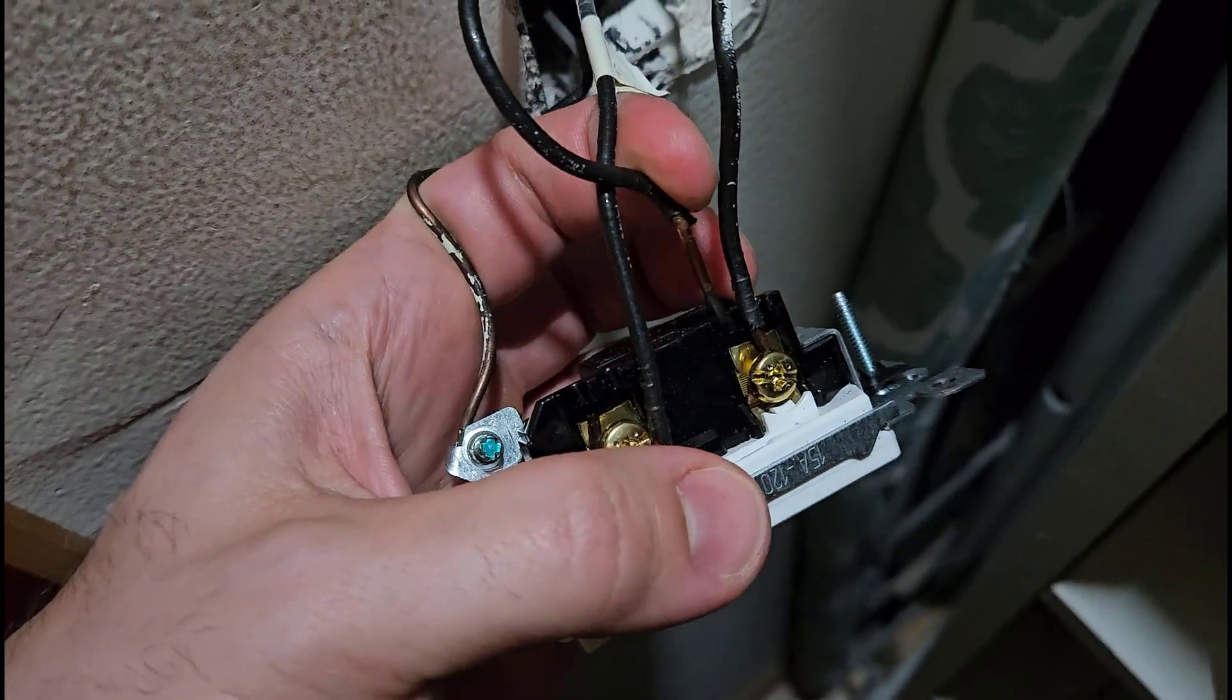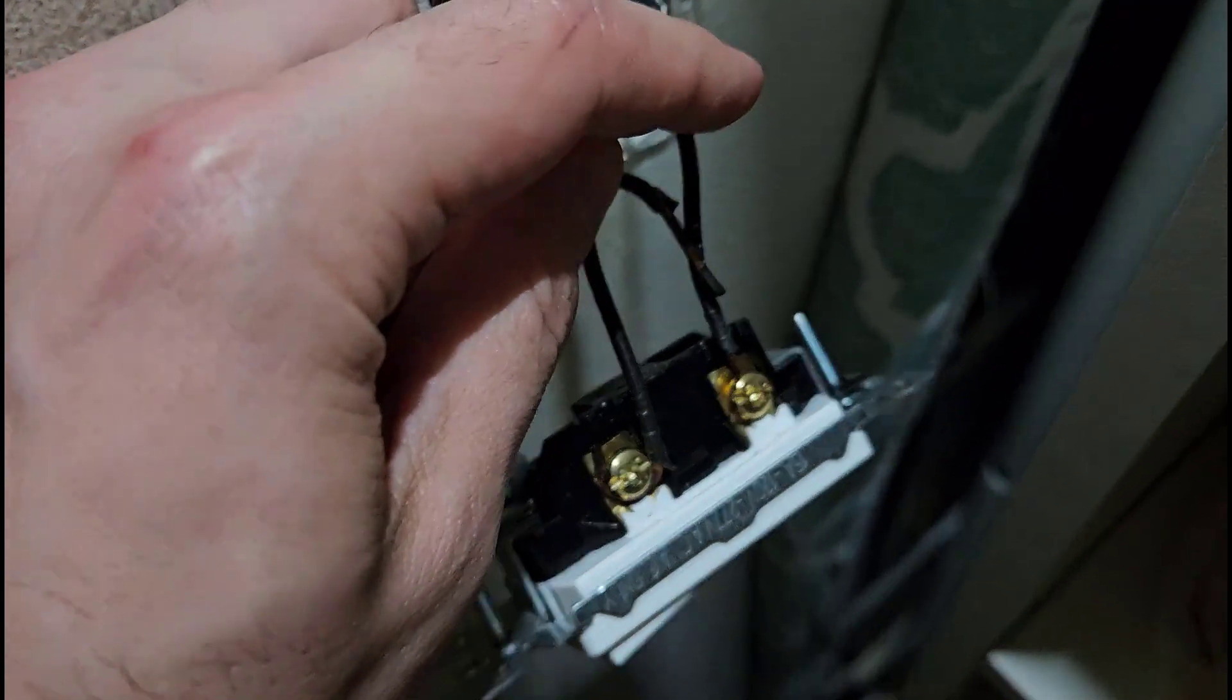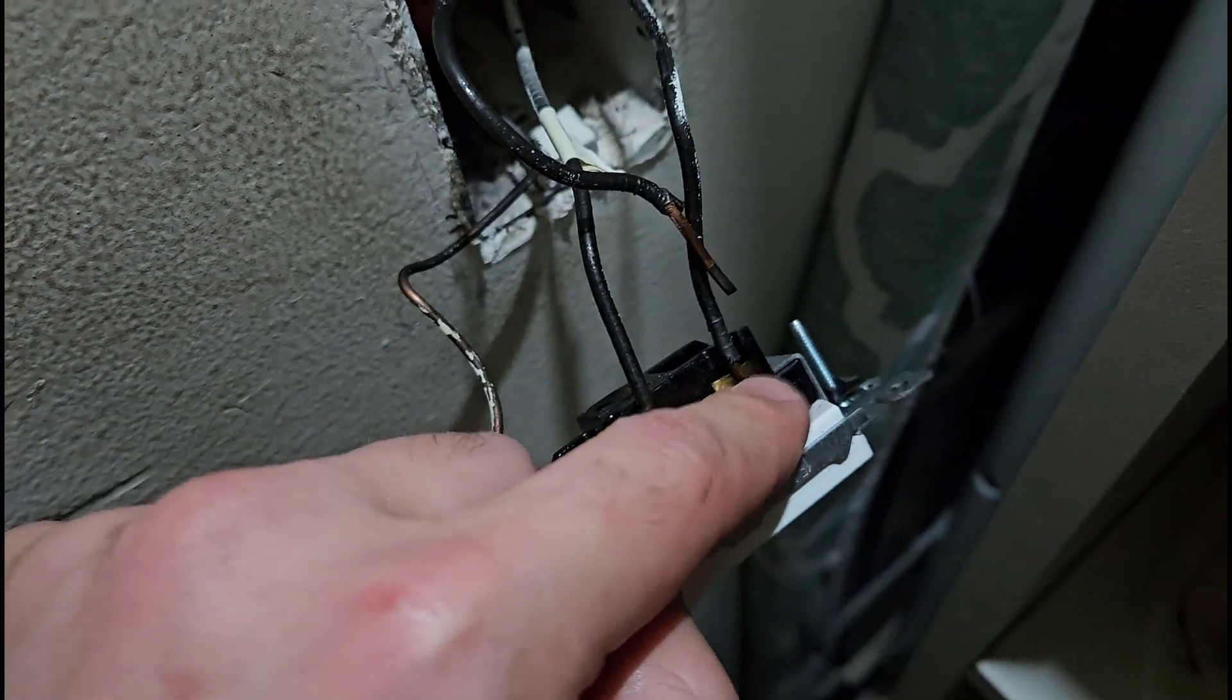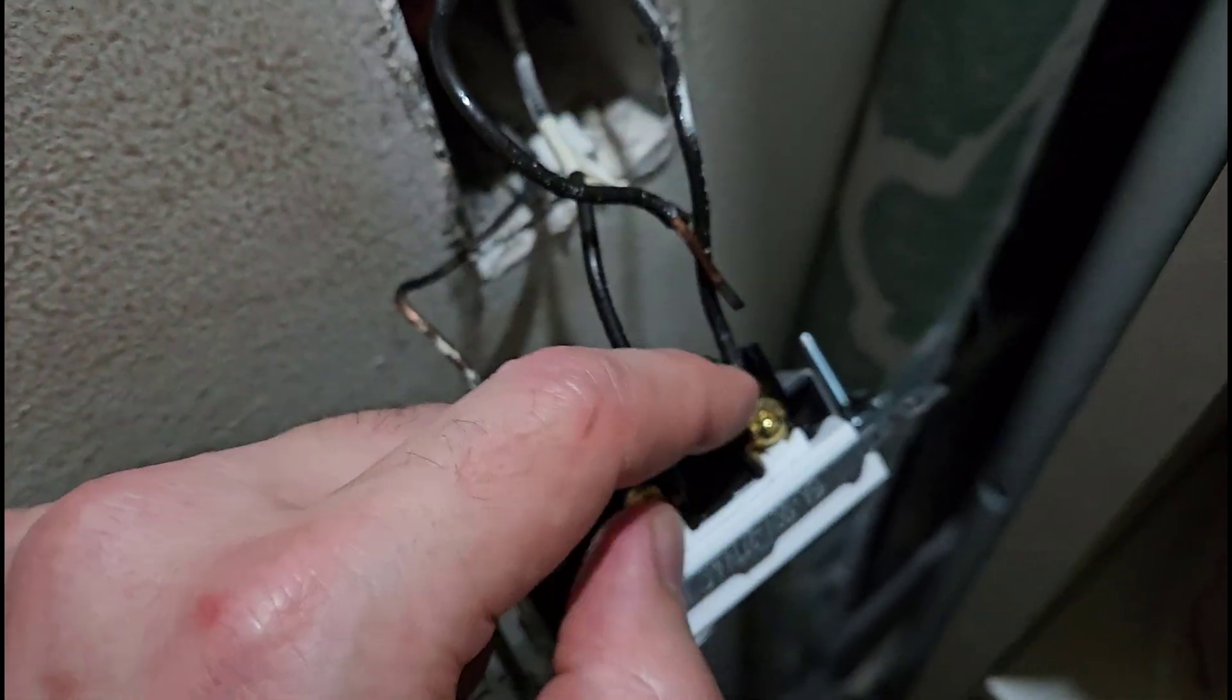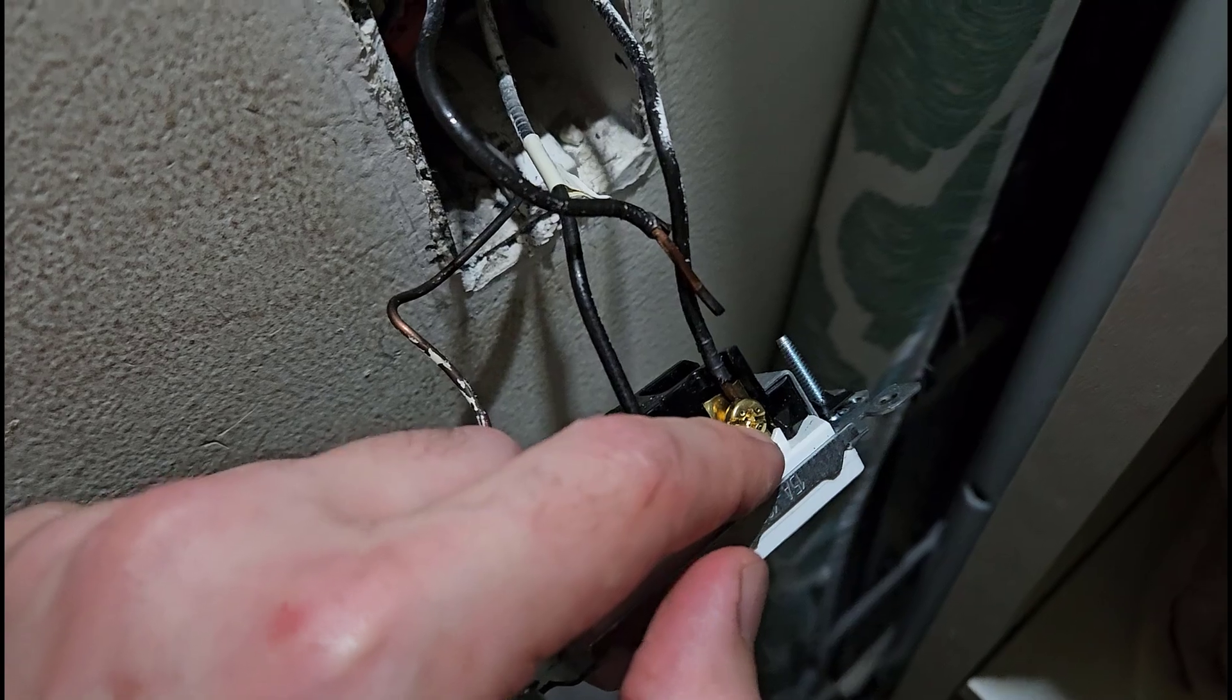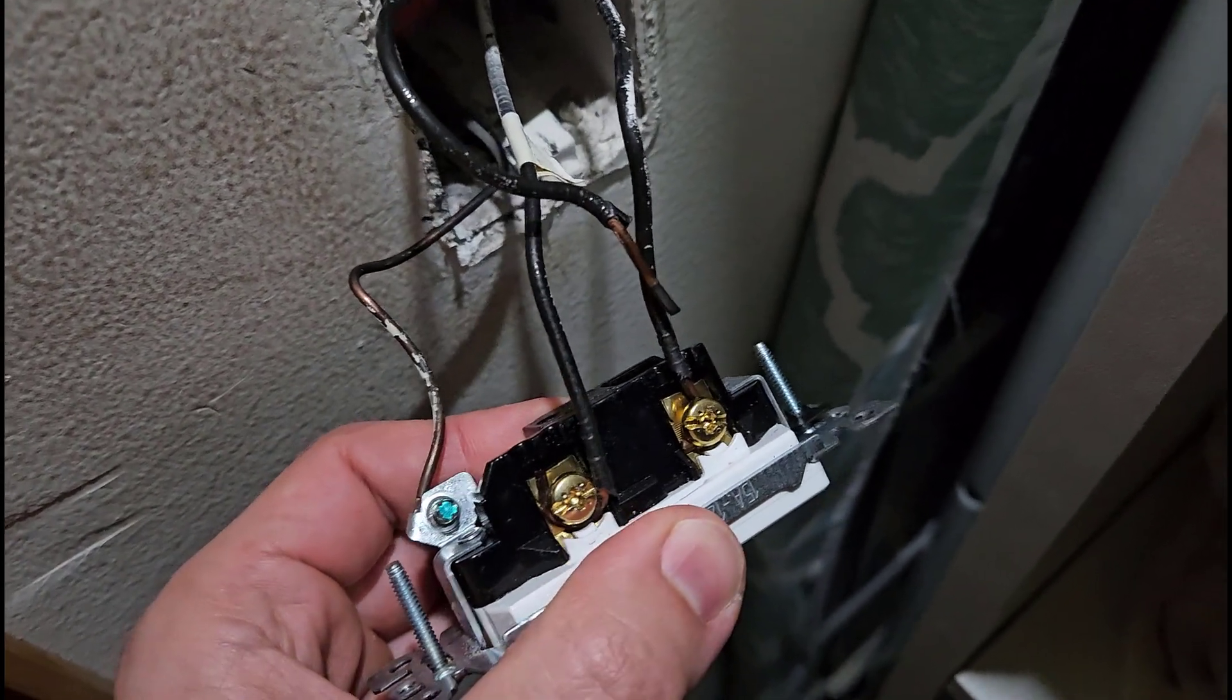So the proper way to do that is to use a wire nut separately to connect these two wires and then run a third wire to the screw, as opposed to trying to cram both wires into the screw or pushing one wire into the hole and one wire into the screw as it was previously. So we're going to redo that and show you the proper way to do it.